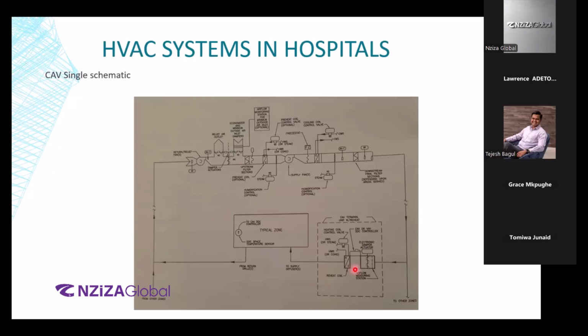This is actually a normal operation. I know the heater is necessary. The problem was whether it is necessary for every room, or whether it has to be controlled depending on the required temperature in the room. Right, exactly. Thinking it is compulsory. No, not compulsory. If there is enough evidence that you do not require it and a colder temperature is fine going into the room, it is fine. But I would recommend, if it is a patient room, give it so that you can modulate the temperature of the air properly over there. Right?